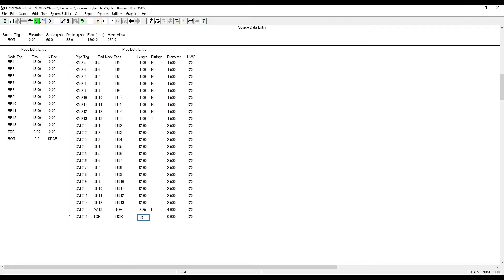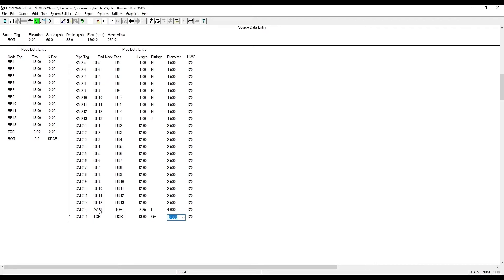Now we go TOR to BOR with an elevation difference of 13 feet, so that's the length of the pipe, an alarm check valve, and a gate valve. And again we're staying with 4 inches.